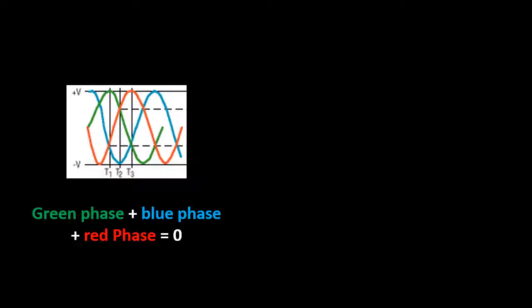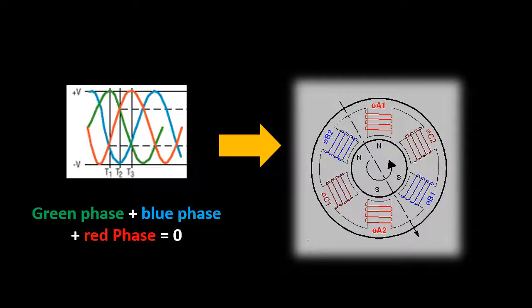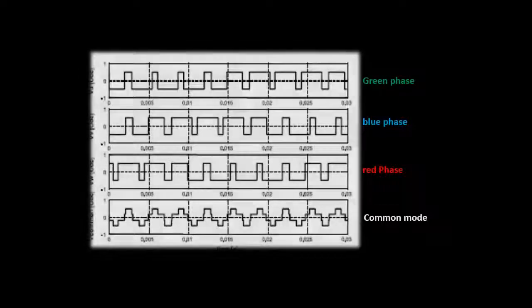An ideal three-phase sinusoidal power supply will deliver a balanced and symmetrical voltage to the motor, which ideally has its stator poles placed at exact positions around the rotor, in order to consume the voltage in a balanced way. However, the reality of this is quite different. The PWM action of a VSD unbalances the supply fed to the motor, which induces a voltage on the rotor at a frequency equal to the VSD's switching frequency. This is in the kilohertz range.